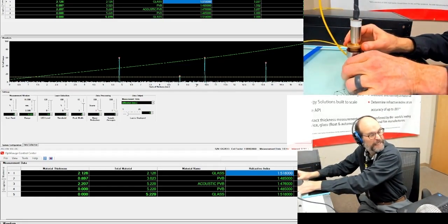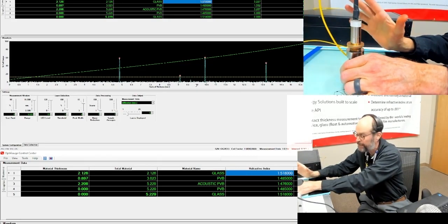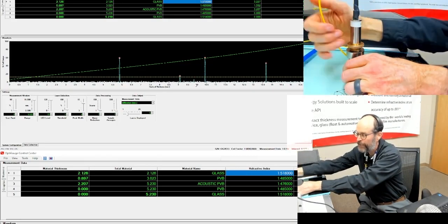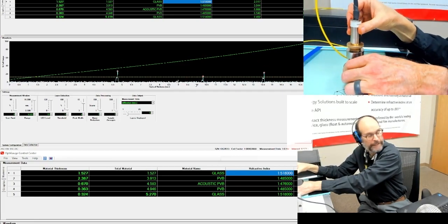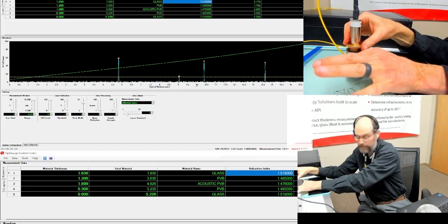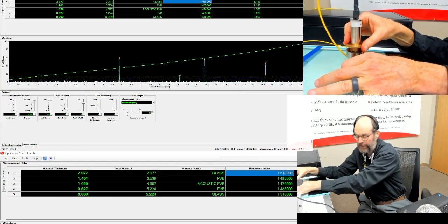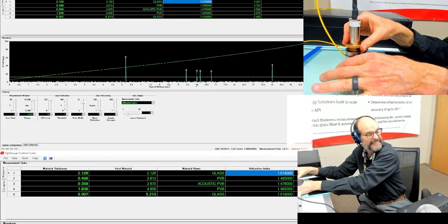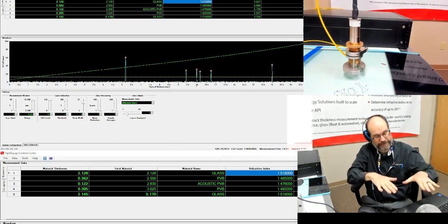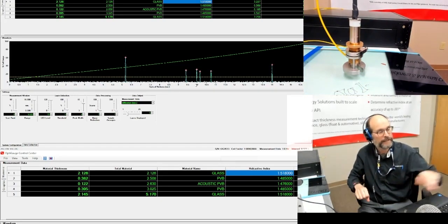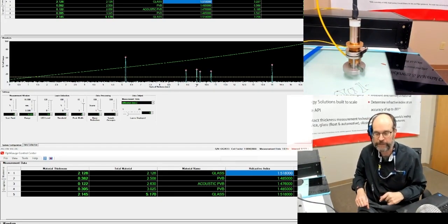And that's what you've got to do. And by the way, just a little practical thing: since this is a fiber, you don't want to spin this to make a height adjustment. You want to spin on the glass. And see how when I set the height just right, I get all my 5 layers in.